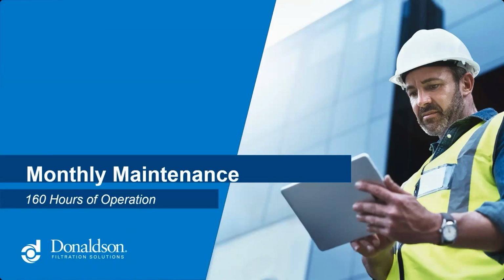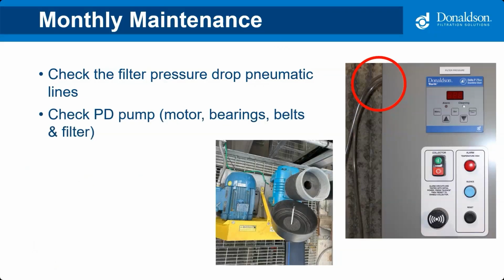All right, monthly maintenance. On a monthly basis, you want your team checking the pneumatic lines that go to your gauge. A few slides ago, I showed you a basic manual gauge that shows inches of water. On the right-hand side here is a control panel for a dust collector, where those are now being routed into a digital gauge, but it's the same thing. They both use similar lines. You can see there's two clear nylon air lines that are carrying low pressure air, so we can read that pressure drop on the filter.